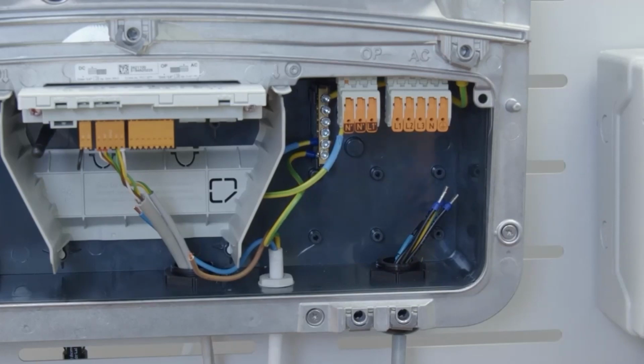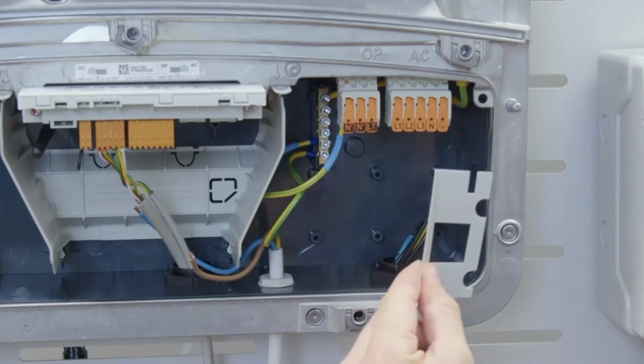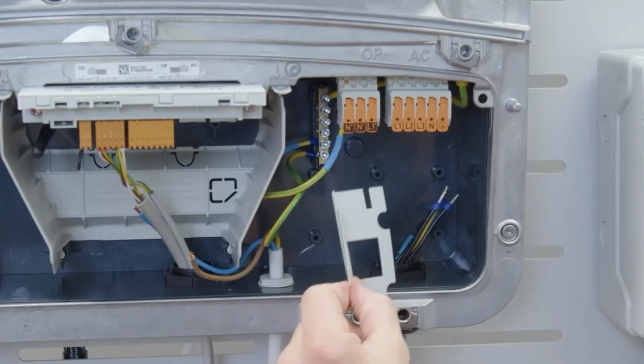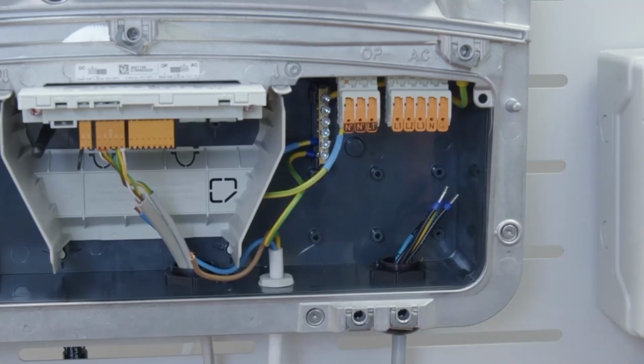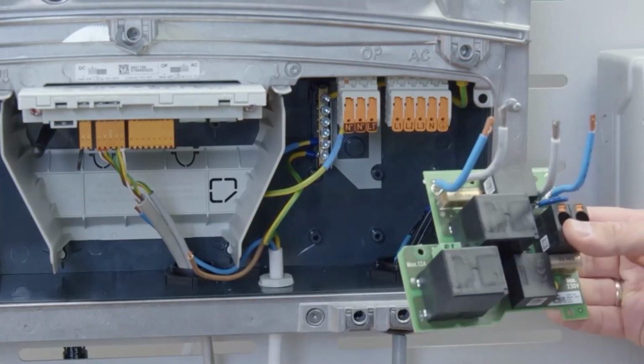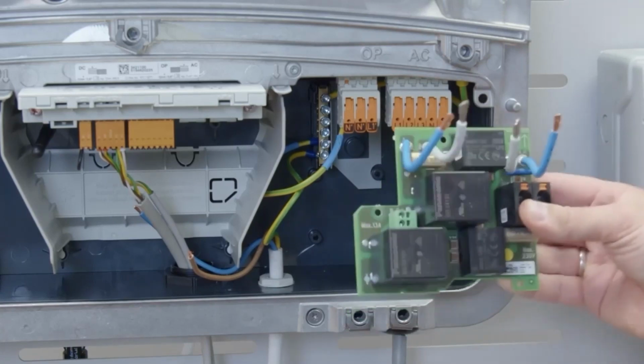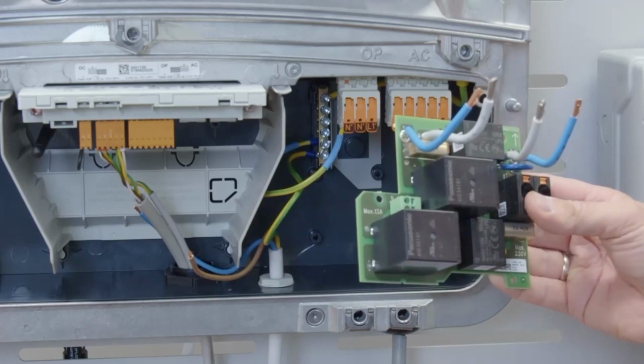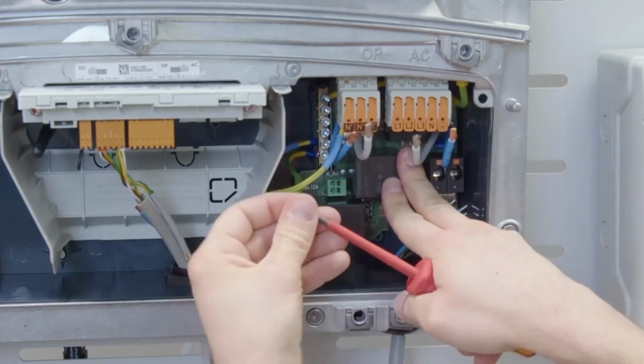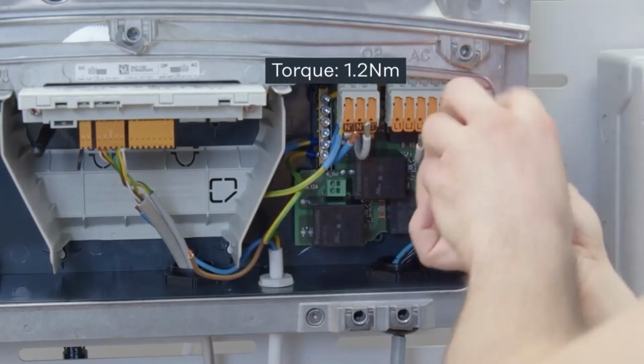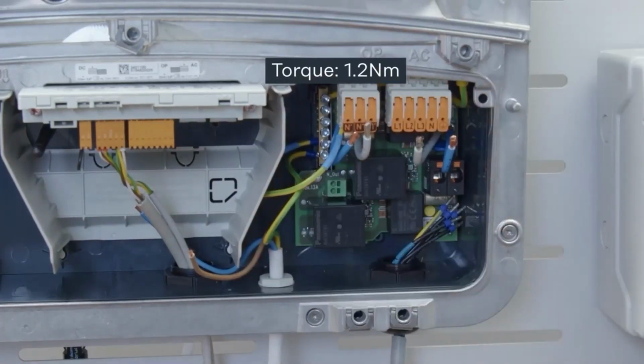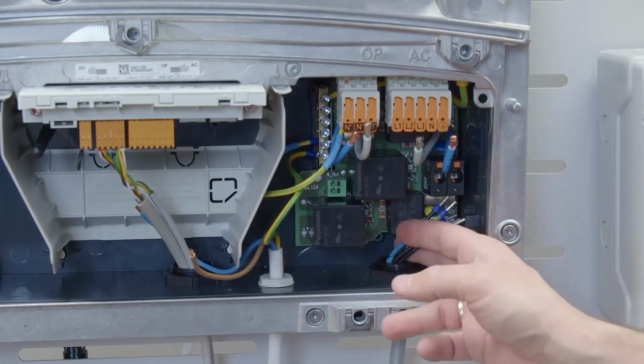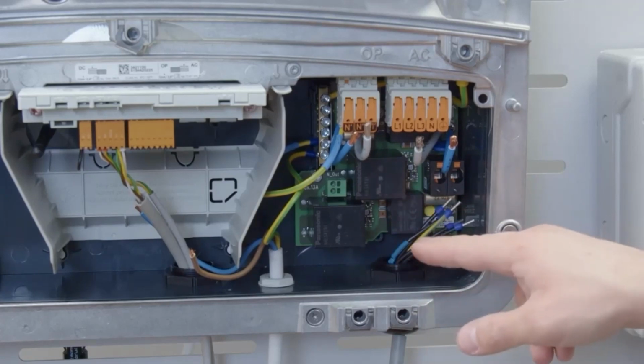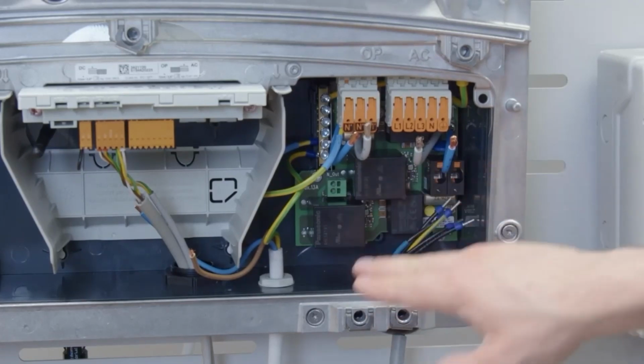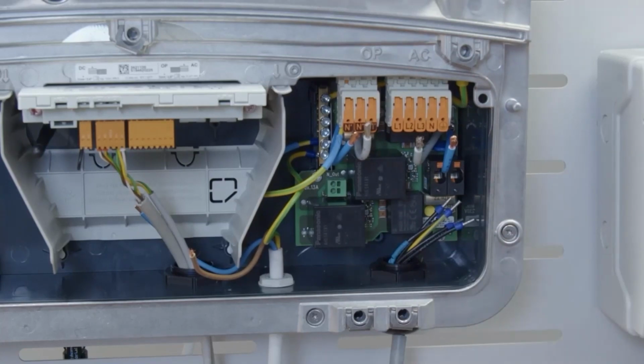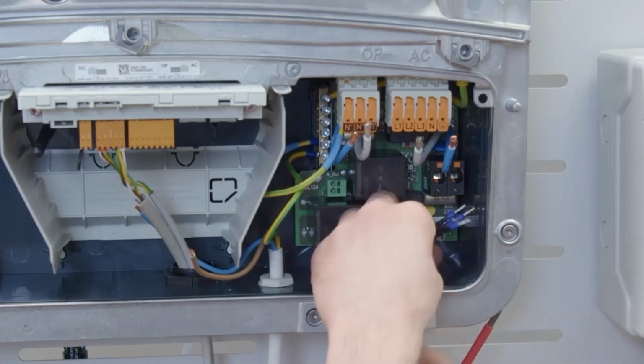When we have installed the protective earth cable, next we want to put in the isolation plastics to make sure that the PE connection is not connected to the PC board of the PV point. After that, you are now able to install the PC board of the PV point directly into the base of the inverter with the 4 screws that you get delivered with the package. Please make sure to secure the screws of the PV point comfort with 1.2 Newton meters of torque. After we have installed the PC board, we can next start to connect the cables to the inverter as well as to the PV point load.